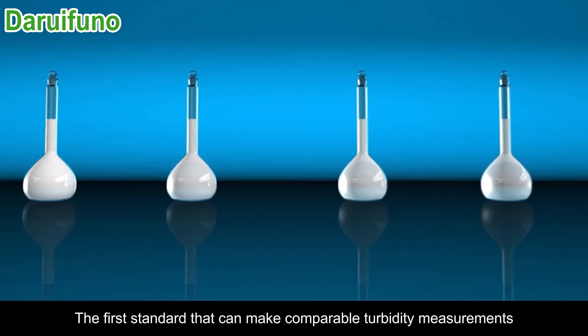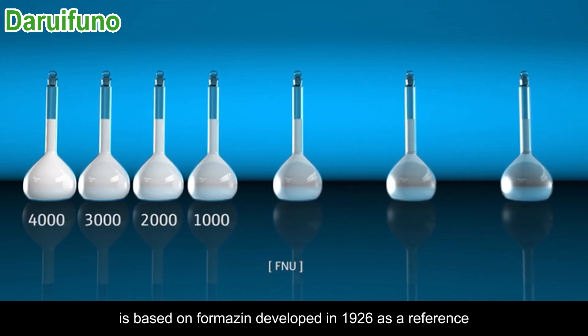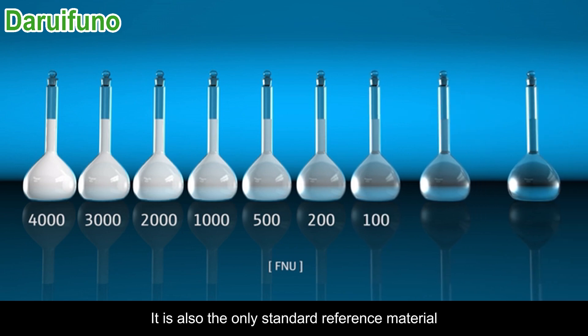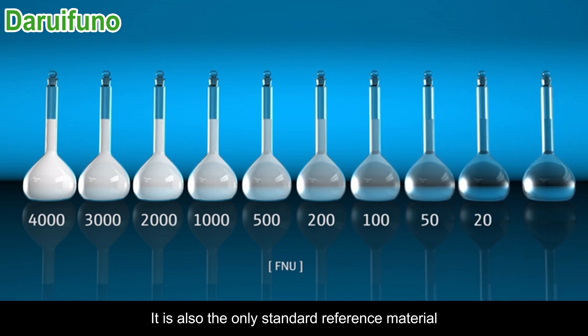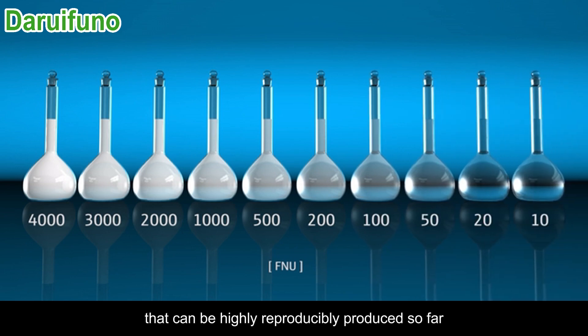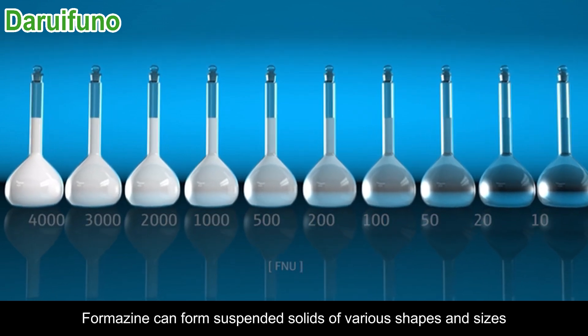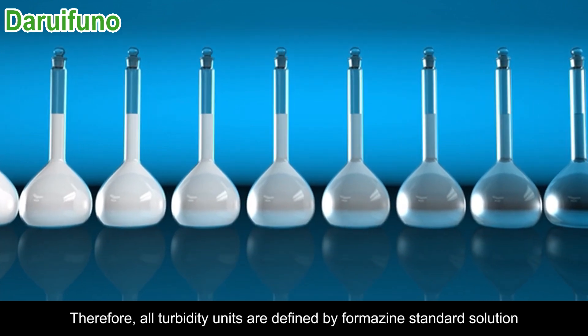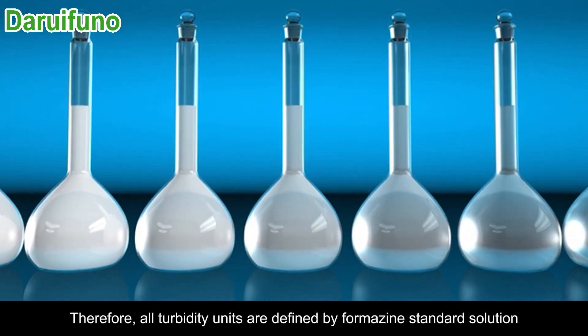The first standard that can make comparable turbidity measurements is based on formazine, developed in 1926 as a reference. It is also the only standard reference material that can be highly reproducibly produced so far. Formazine can form suspended solids of various shapes and sizes; therefore, all turbidity units are defined by formazine standard solution.